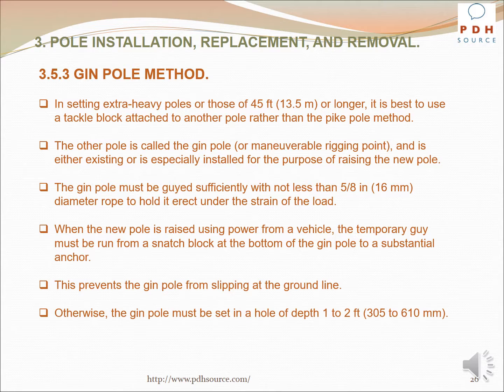With regard to the gin pole method, in setting extra heavy poles or those 45 feet or longer, it is best to use a tackle block attached to another pole rather than the pike pole method. The other pole is called the gin pole or maneuverable rigging point and is either existing or is especially installed for the purpose of raising the new pole. The gin pole must be guyed sufficiently with not less than 5/8 inch diameter rope to hold it erect under the strain of the load. When the new pole is raised using power from a vehicle, the temporary guy must be run from a snatch block at the bottom of the gin pole to a substantial anchor. This prevents the gin pole from slipping at the ground line. Otherwise, the gin pole must be set in a hole of depth 1 to 2 feet.